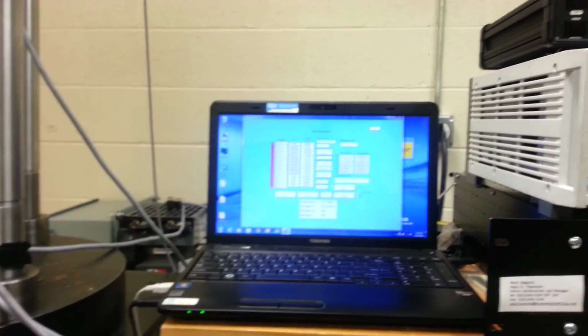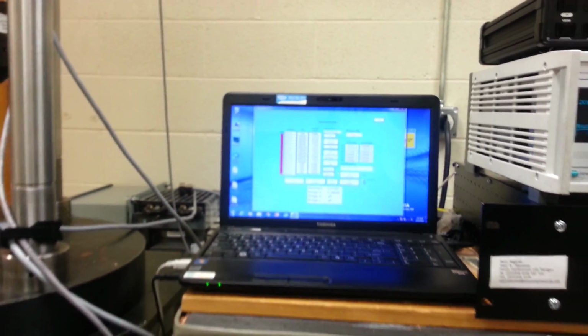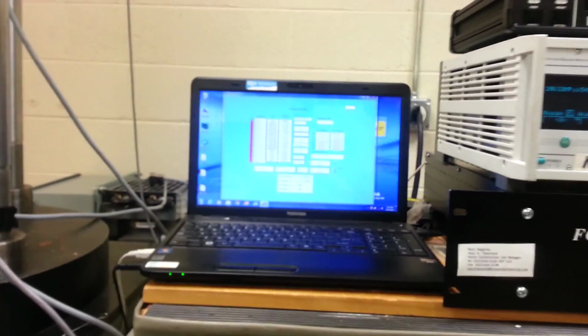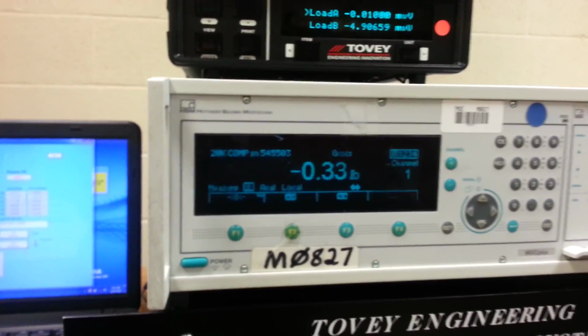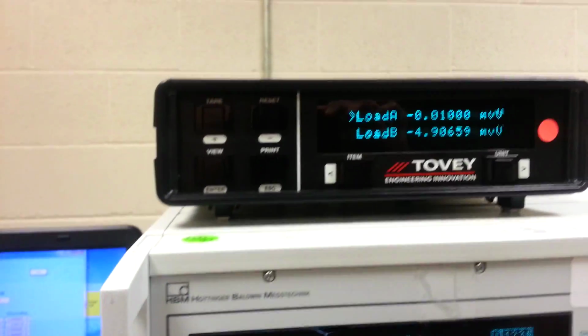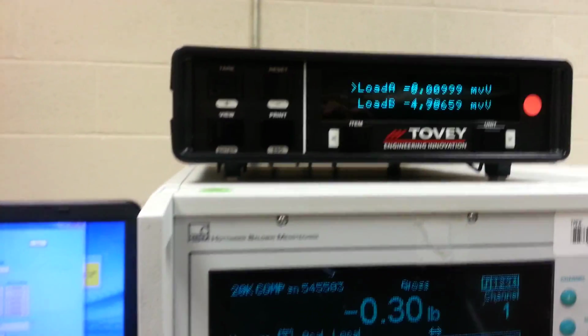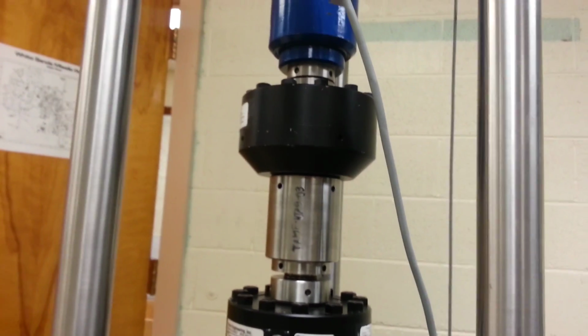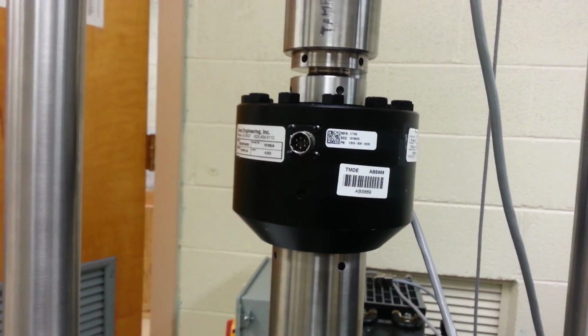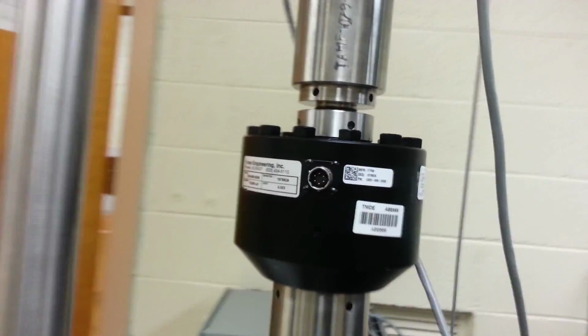Okay, this is the calibration of a 20,000 pound load cell using the new Tovey engineering system that is getting fielded to USADA. I have my MGC Plus here from the customer and the 9150, which is the readout for the Tovey engineering. And right now I have this 60,000 pound spacer. It's what we use it for.